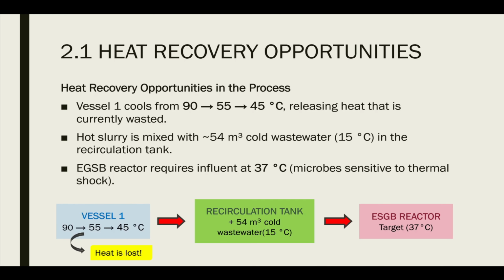As we know, vessel 1 goes through 2 cooling steps. First, it cools from 90 down to 55 degrees, and then from 55 to 45 degrees. Every time this cooling happens, a large amount of heat is released, but at the moment, this heat is just lost to the environment. After this, the hot slurry is mixed with about 54 cubic meters of cold wastewater at around 15 degrees in the recirculation tank. Because the wastewater is much colder, this mixing can cause the overall temperature to drop very quickly, which can be a problem because the EGSB reactor that comes after needs the liquid to stay close to 37 degrees, as the microbes inside the reactor are very sensitive, and if the temperature is too low, it can shock them and reduce the efficiency of the process. So we need to find a way to reuse that wasted heat to keep things stable.